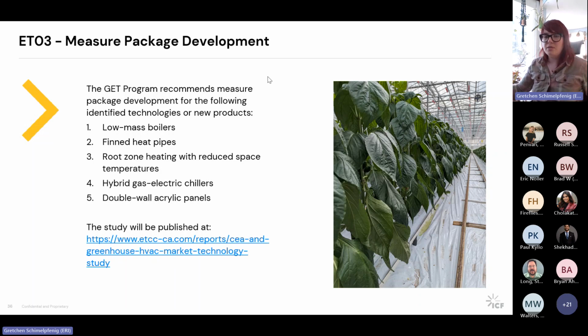Absolutely. Something to think about with low mass boiler design is how the boiler system is going to serve the different process activities happening in the greenhouse. One thing I've heard quoted from greenhouse experts is that when you've seen one greenhouse, you've seen one greenhouse. So in my experience, it's very important for these systems to be customized to each facility. Understanding the amount of water used for things like irrigation and fertigation might be needed if the grower wants to use the boiler system to temper their water. That's something I've seen in my area in Vermont; it may not be as common or necessary in California.